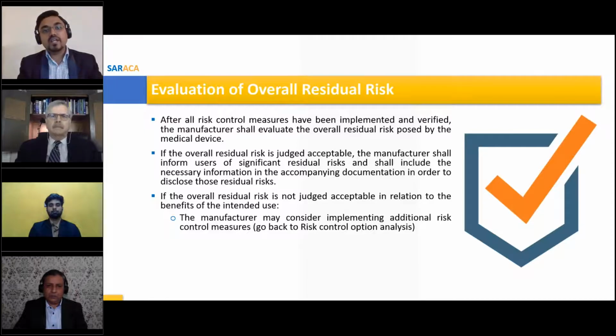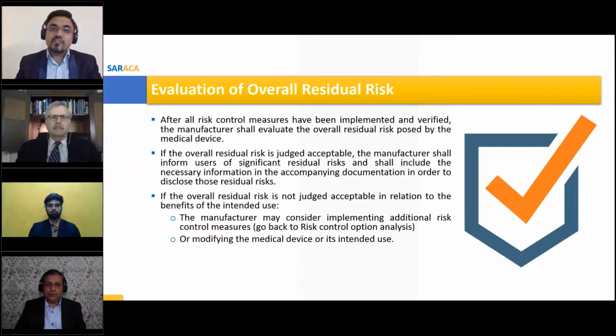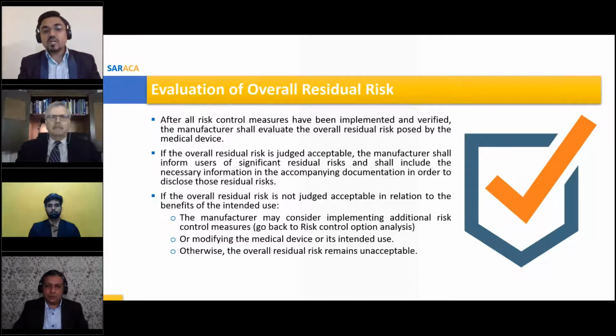If you find with those criteria that the overall residual risks which were evaluated are not acceptable, then the manufacturer, as Sam told you earlier, needs to go to the design phase. Sometimes the manufacturer may consider implementing additional risk control measures. Then he can go back to the risk control analysis and implement more risk control measures. But if that is not possible, then the manufacturer needs to modify the medical device, going to the design phase and changing the design of the medical device or the intended use. Otherwise, the overall residual risk remains unacceptable.